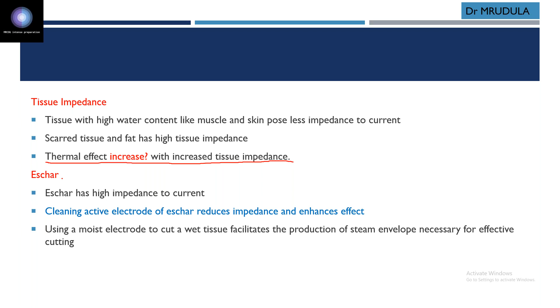Okay, so eschar, or a black scarred area, forms when you use this cautery, and you can see it on this instrument. So it has a high impedance to current. Cleaning the active electrode of eschar reduces impedance and enhances the effect. Using a moist electrode to cut wet tissue facilitates the production of the steam envelope necessary for effective cutting. So you can see this moist electrode functions very effectively.